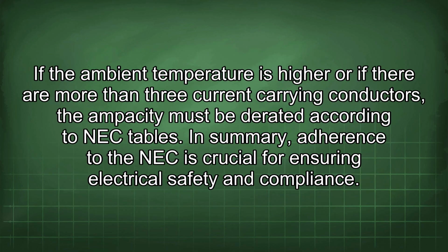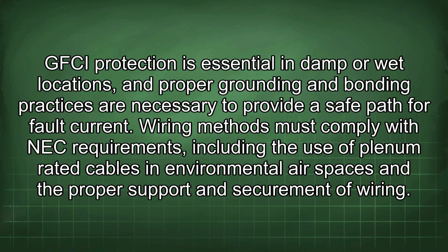If the ambient temperature is higher, or if there are more than 3 current carrying conductors, the ampacity must be derated according to NEC tables. In summary, adherence to the NEC is crucial for ensuring electrical safety and compliance. GFCI protection is essential in damp or wet locations, and proper grounding and bonding practices are necessary to provide a safe path for fault current.